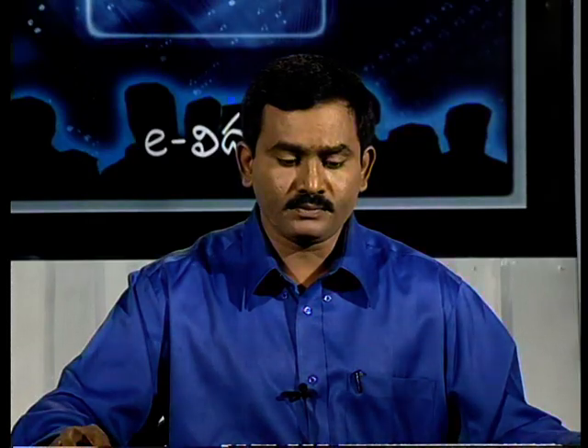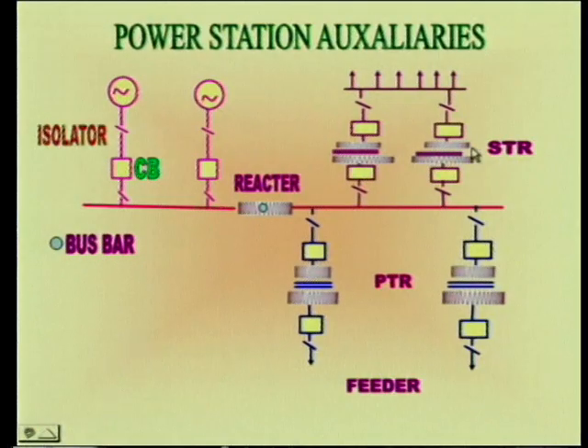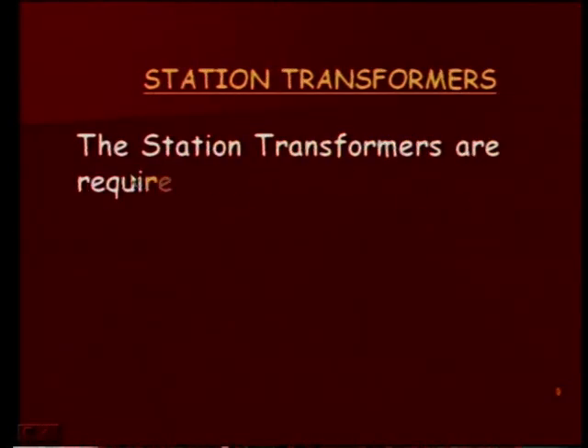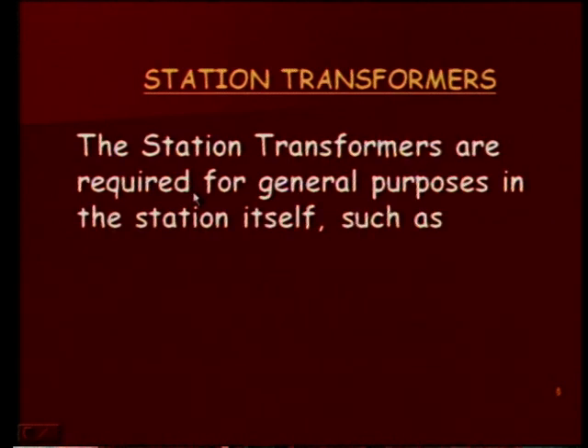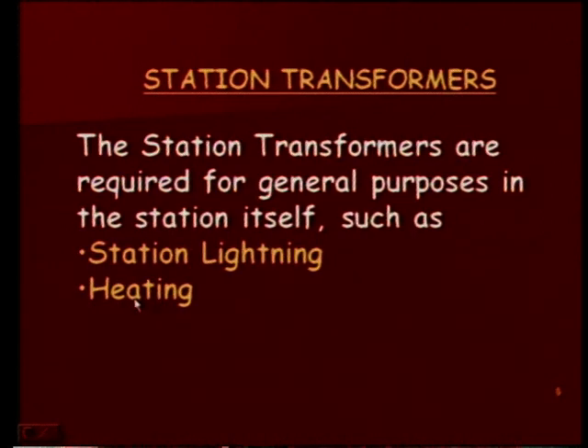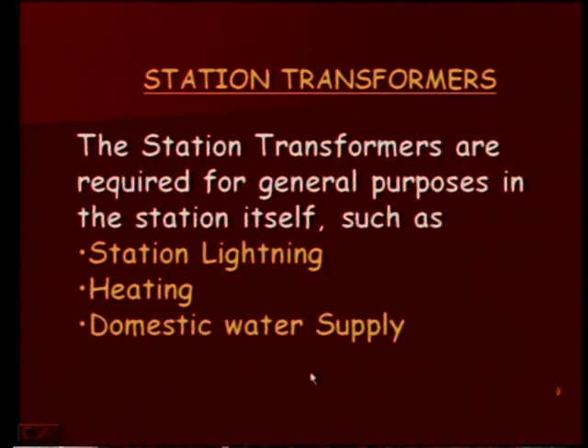Another important one is the station transformer. The station transformers are required for general purposes in the station itself, such as station lighting, heating, domestic water supply and battery charging.